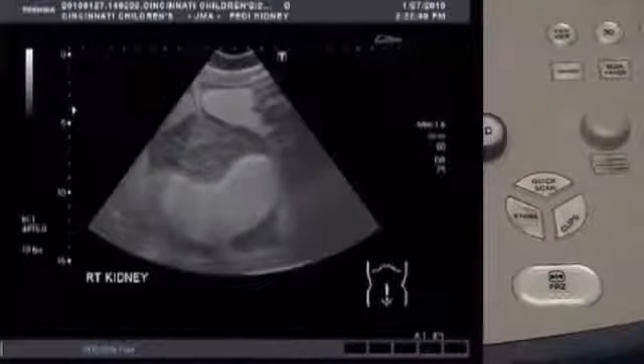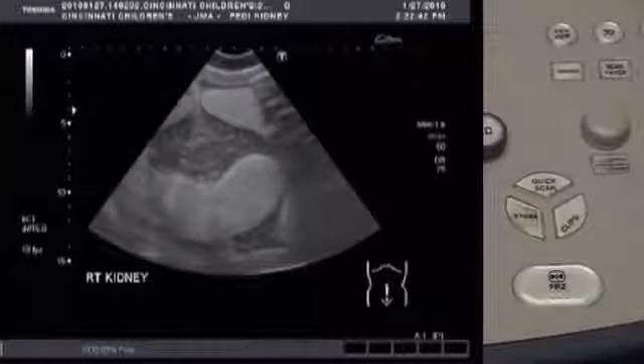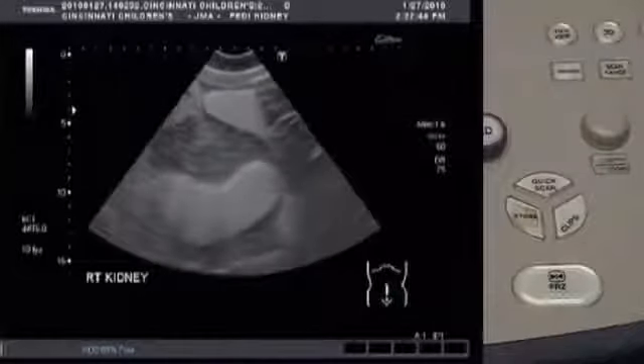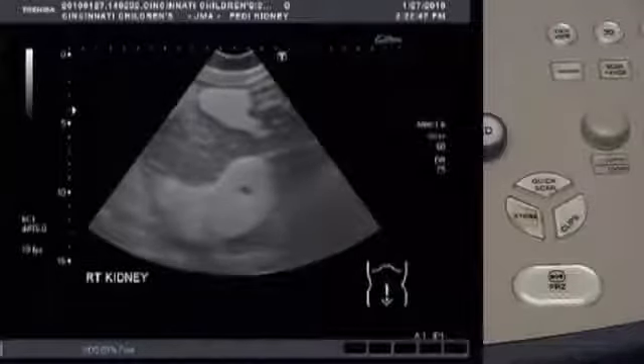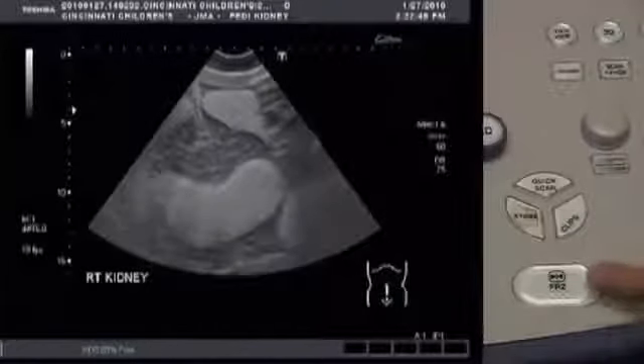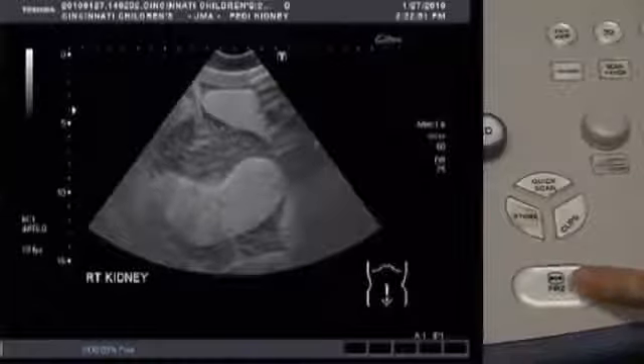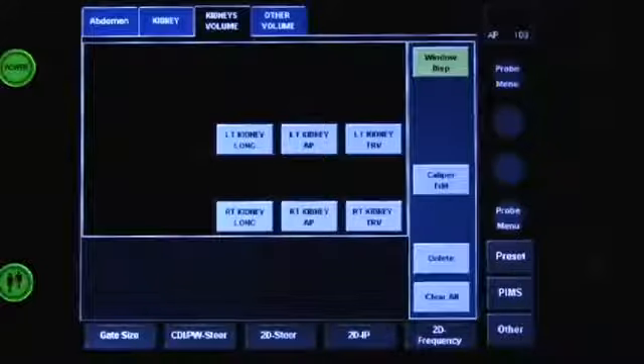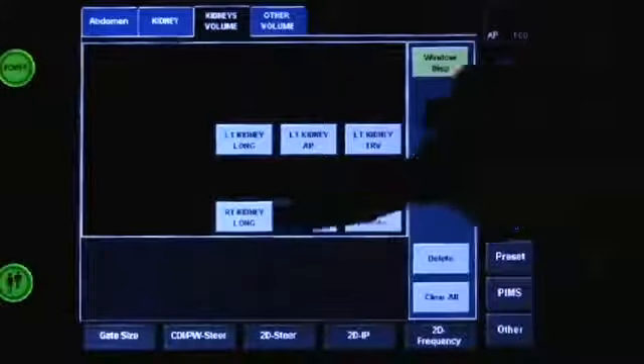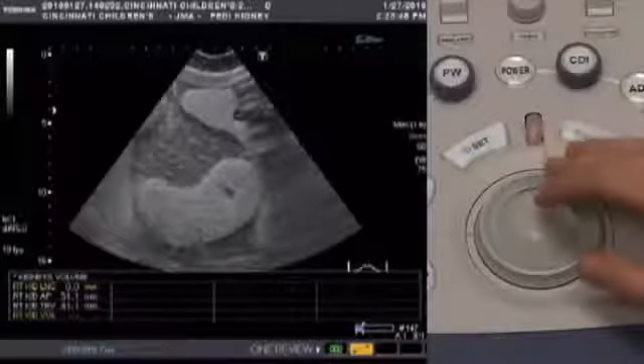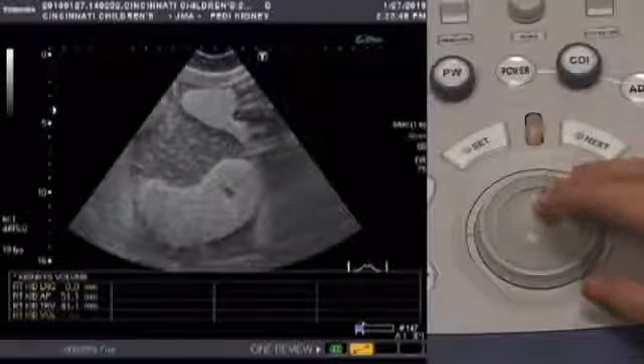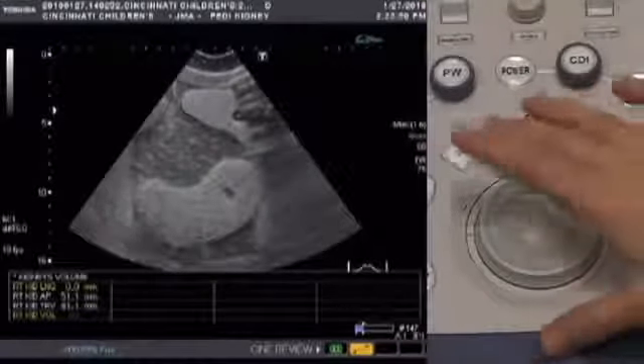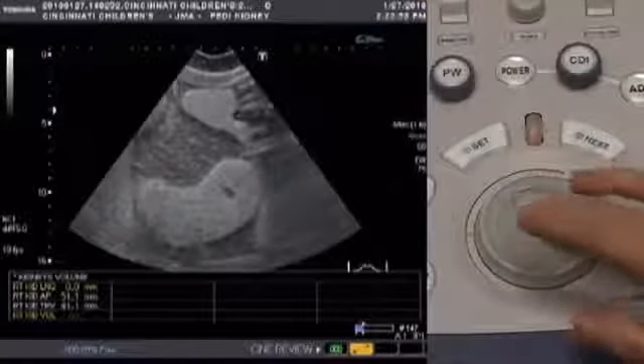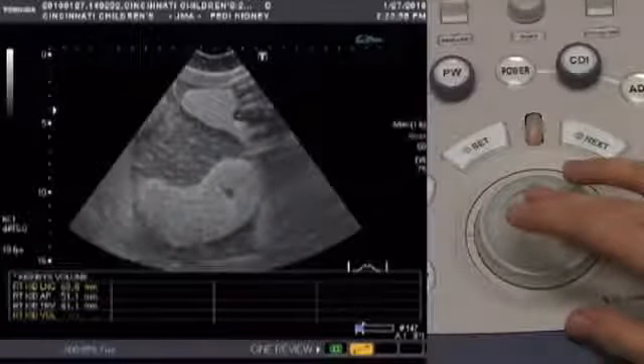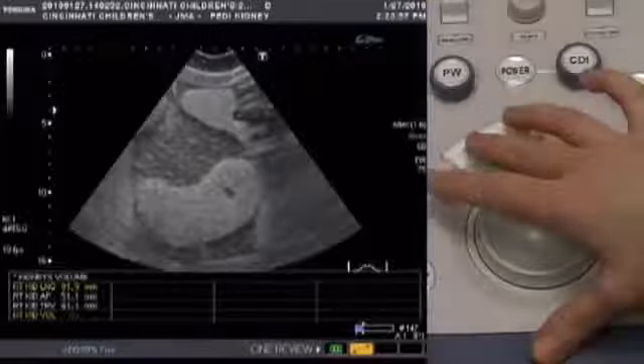Scan the phantom in the longitudinal axis until you have a good view of the kidney. Then freeze the image by pressing FRZ. Now we're going to be measuring the longitudinal axis of the right kidney, so press that button on the touch screen. Using the trackball again, move to one edge of the kidney and use set to mark it, and then go to the other edge of the kidney using the trackball and press set again to mark it.